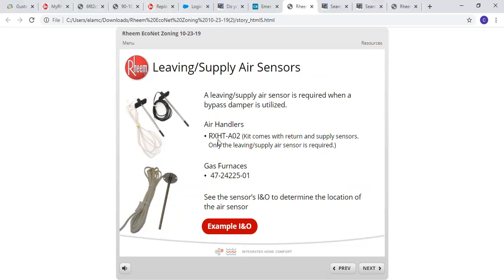The air handlers have a specific sensor, the RXHT-A02 kit, which comes with return and supply sensors. Only the leaving supply air sensor is required. The gas furnace has its dedicated sensor, which is a 47-24225-01. And then see the sensors I and O to determine the location of the air sensor.